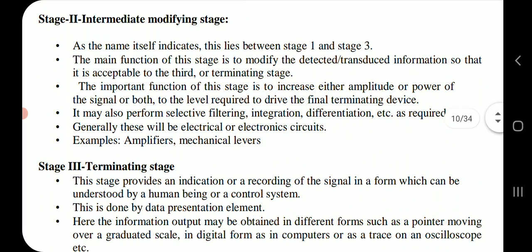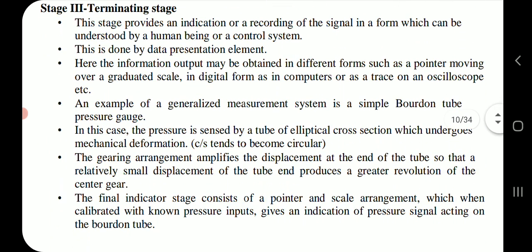Stage 2, intermediate modifying stage. As the name itself indicates, this lies between stage 1 and stage 3. The main function of this stage is to modify the detected transduced information so that it is acceptable to the third or terminating stage. The important function of this stage is to increase either the amplitude or power of the signal or both to the level required to drive the final terminating device. It may also perform selective filtering, integration, differentiation, etc. as required. Generally, these will be electrical or electronic circuits. Examples: amplifiers, mechanical levers.